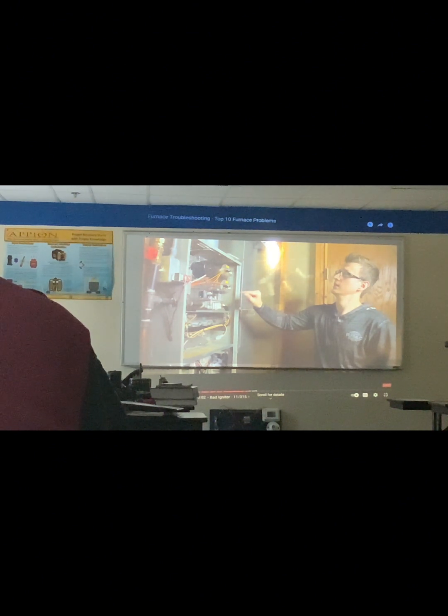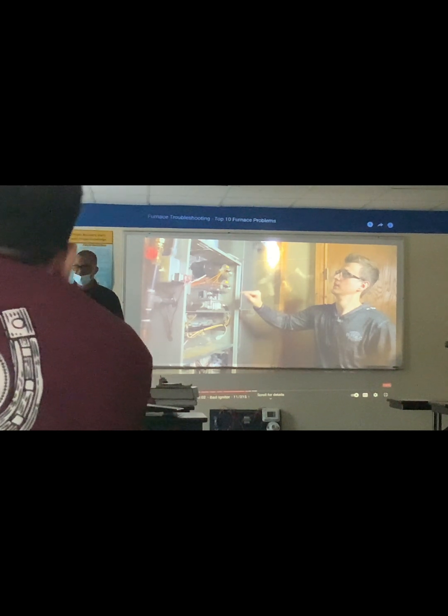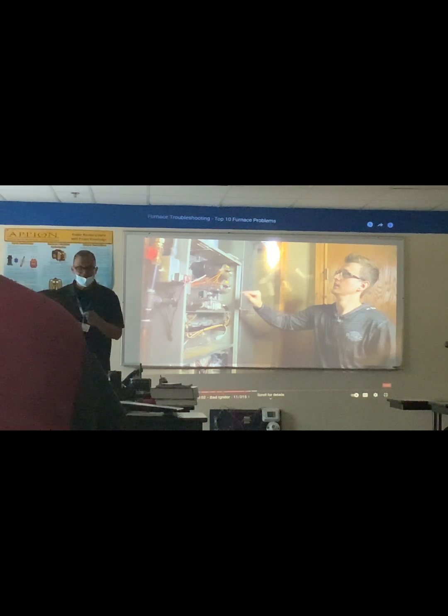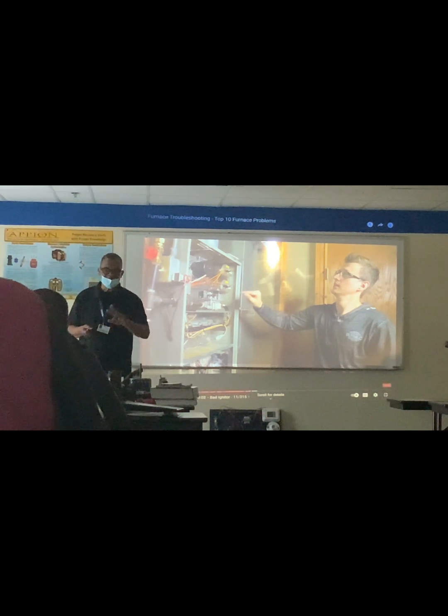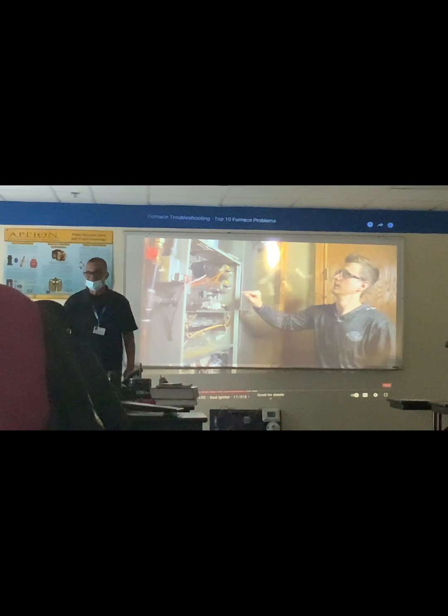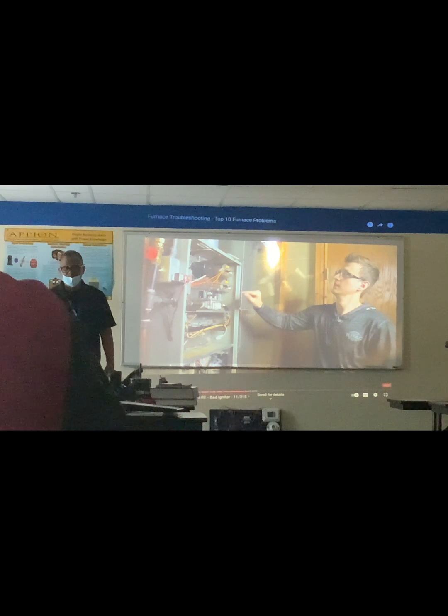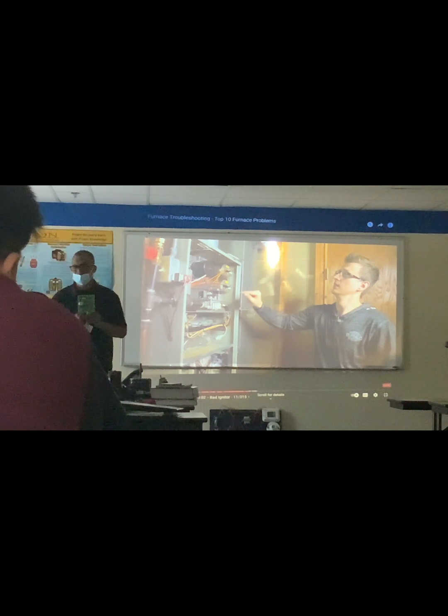But here's one thing too about that igniter: he started off saying flame sensor, correct? And this is one without an angle. I told you some of them are different, that was straight. And so the flame sensor senses flame, even if the sequence says click and you did get a little gas, right? But you didn't mention that. The flame sensor, in less than a second, says, I don't sense no heat. Gas valve closes immediately, 100% shut off, immediately. Doesn't go, wait a minute, it just shuts off. Your blinking light will say no flame, no ignition.